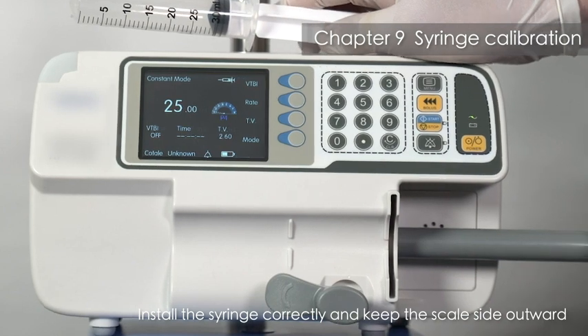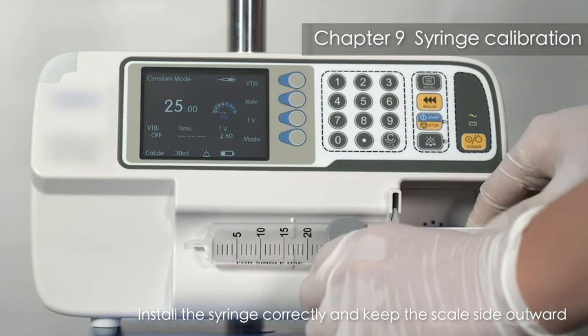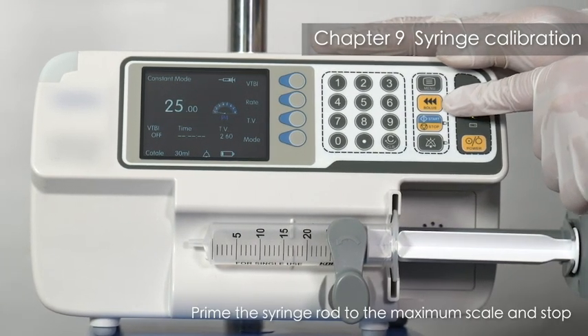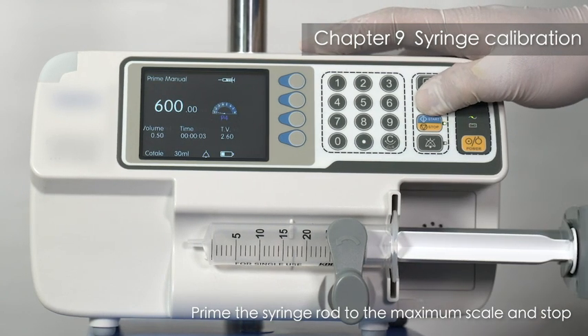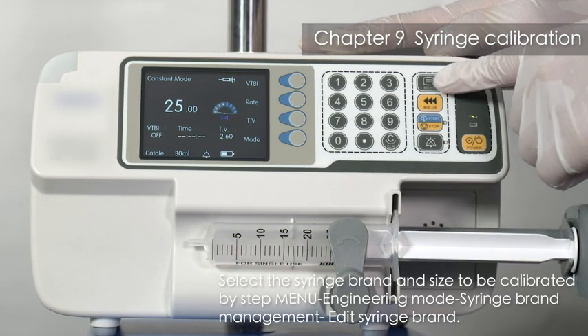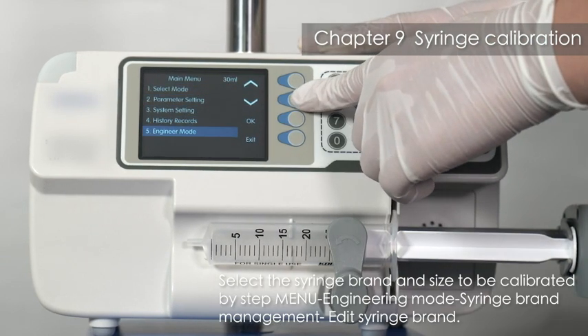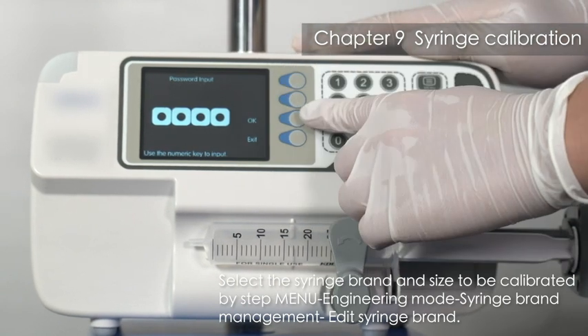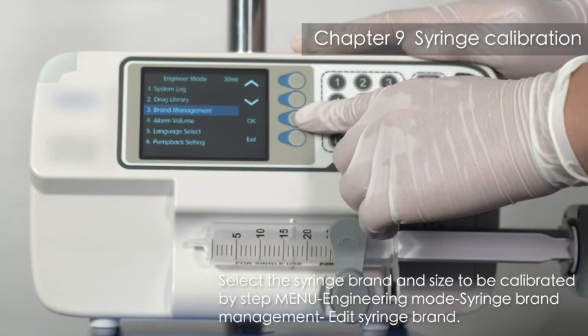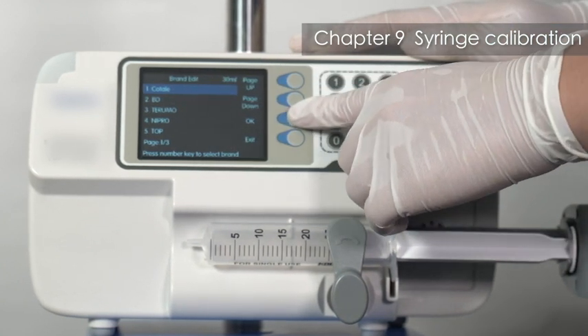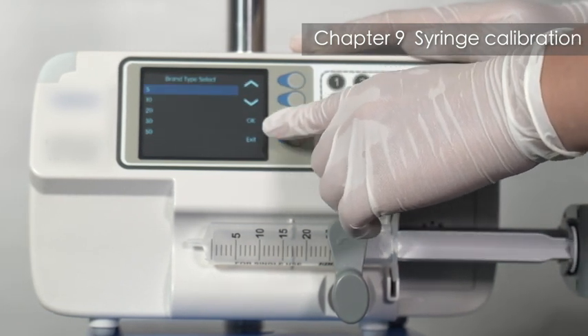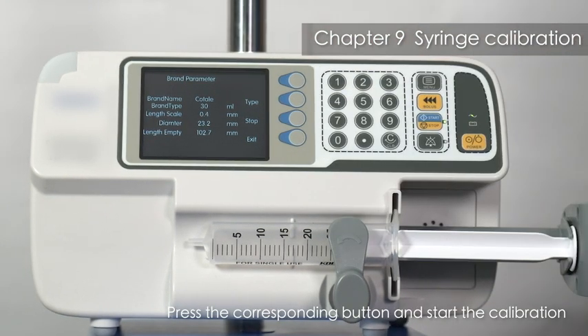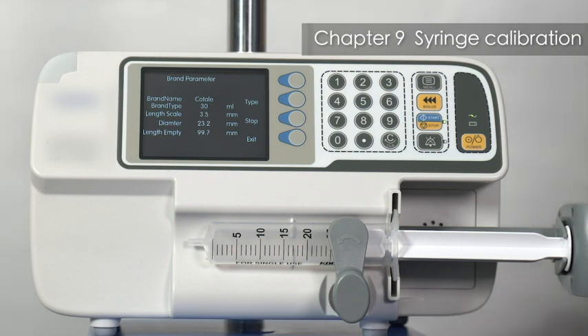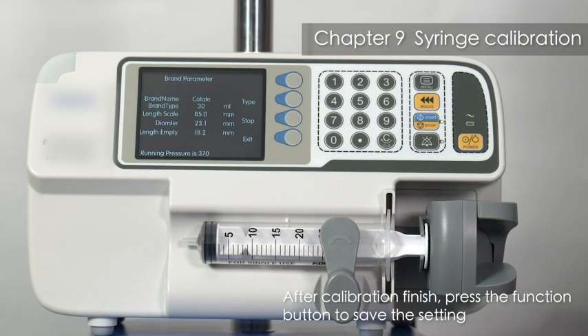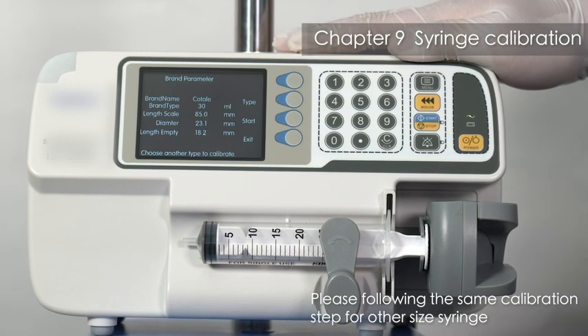Install the syringe correctly and keep the scale side outward. Prime the syringe rod to the maximum scale and stop. Select the syringe brand and size to be calibrated by step: menu, engineering mode, syringe brand management, add a syringe brand. Press the corresponding button and start the calibration. After calibration finish, press the function button to save the setting. Please follow the same calibration step for other size syringe.